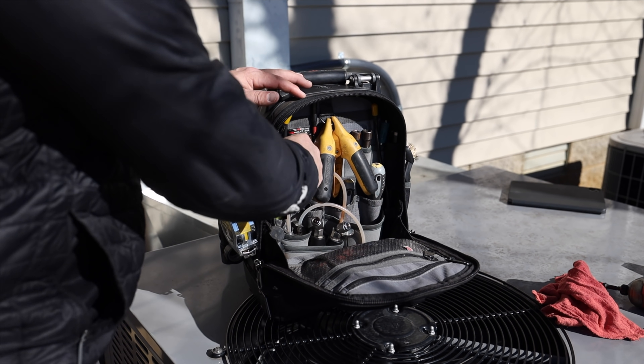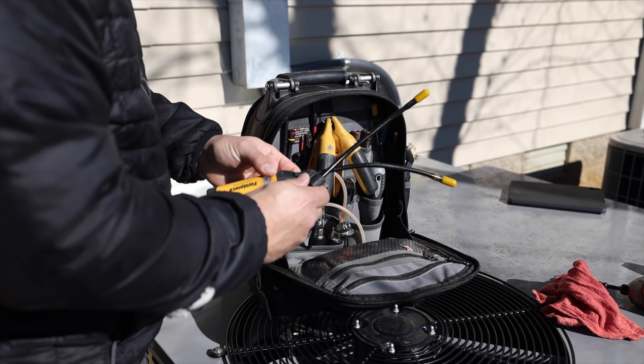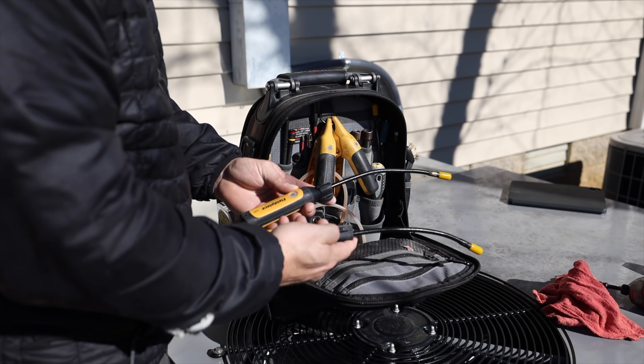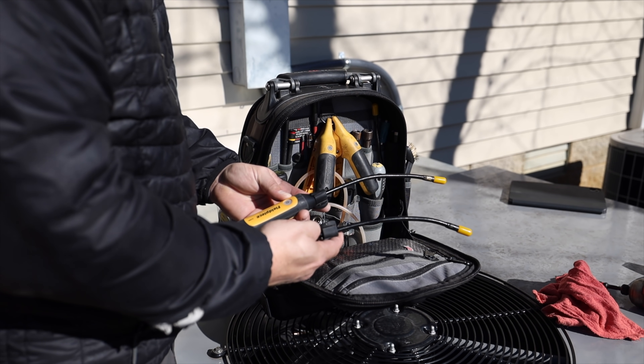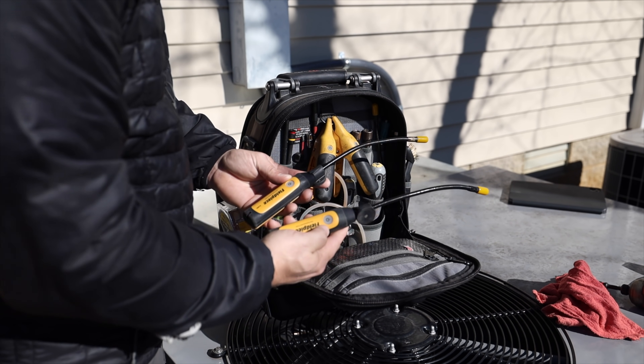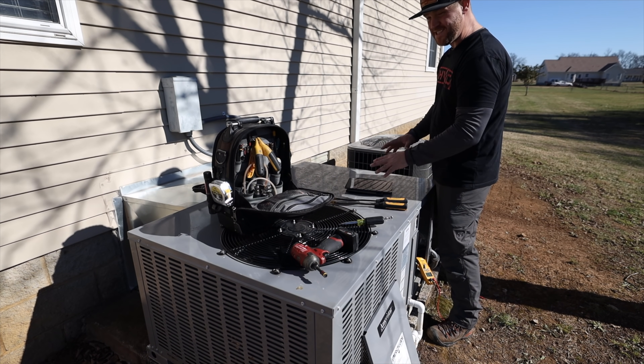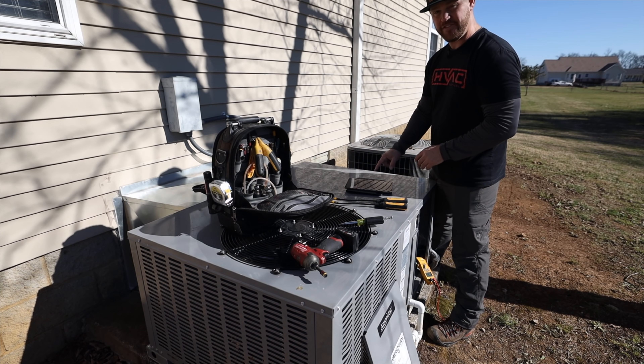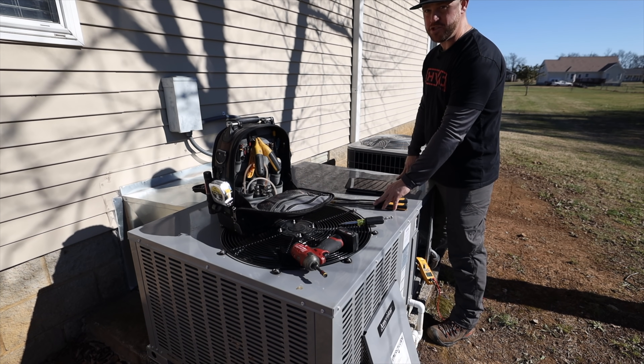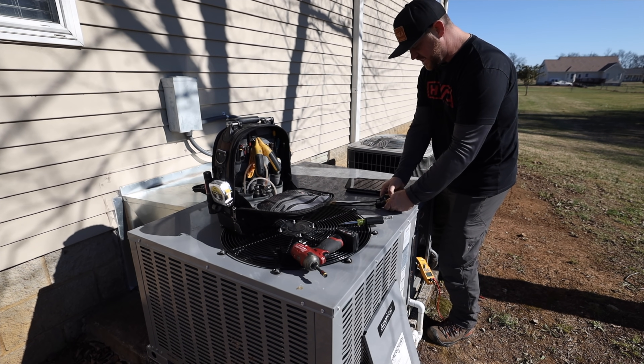The next thing I want to do is grab my Fieldpiece wireless psychrometers — these are the model number JL3RH. These things are awesome. They can Bluetooth up to a thousand feet away to your tablet or smartphone using the Fieldpiece Job Link app. I'm going to put one in the supply and one in the return, and that's going to give me a temperature rise on the electric heat. They just released a new firmware update where these can now read up to 250 degrees inside the ducts — so that's awesome. I'm going to go ahead and get these things turned on.